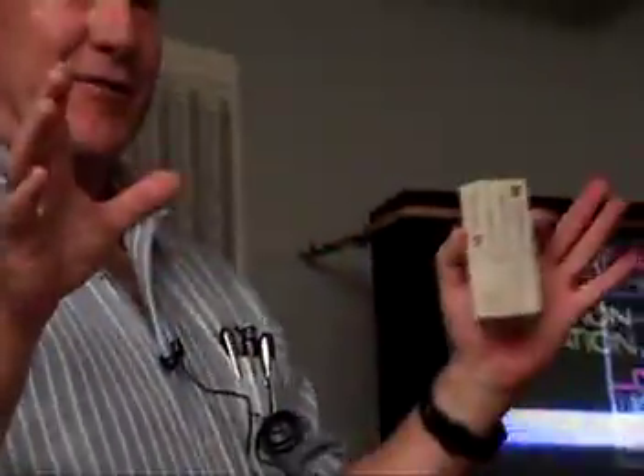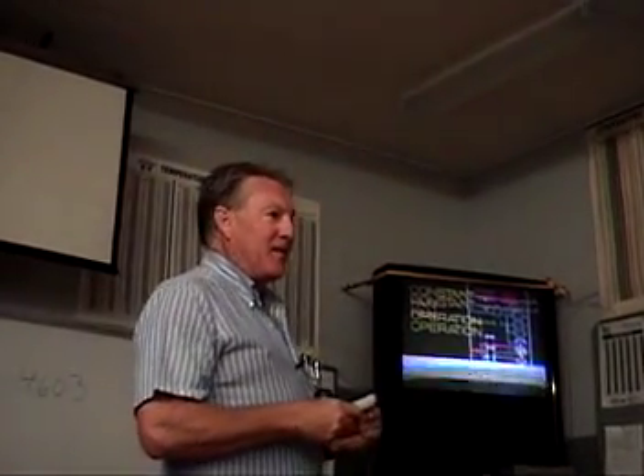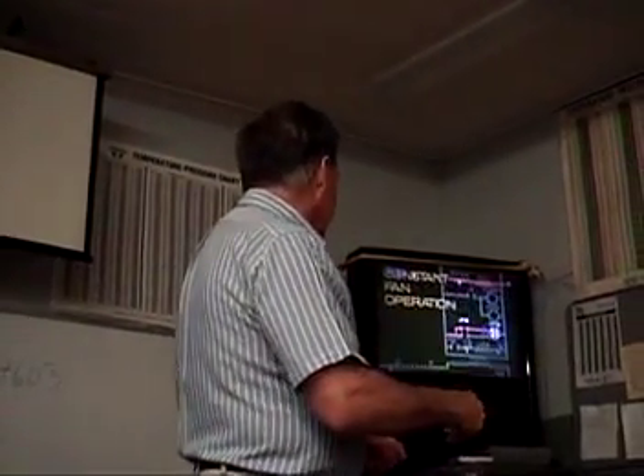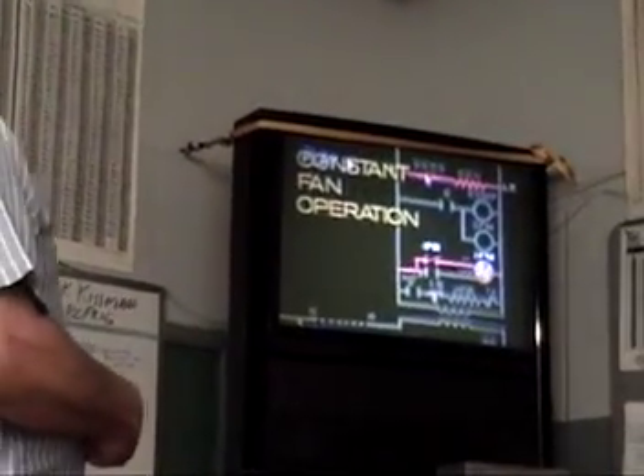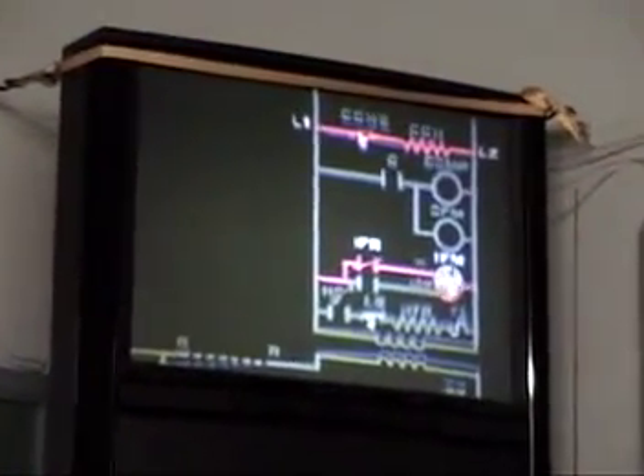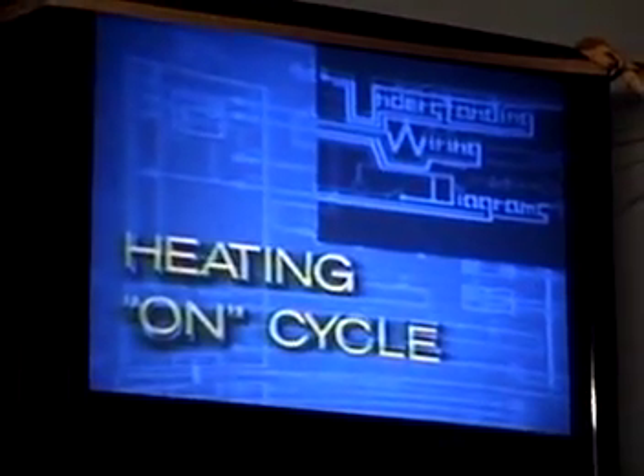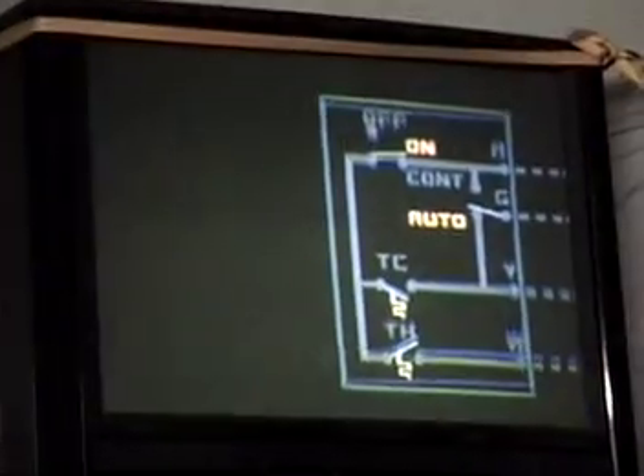Okay, now when I check you off on your competency for wiring up your fan, a couple of you guys, you had it on fan continuous, not auto, and the fan was running like it was supposed to, but it wasn't wired correctly. I switched it to auto, everything went off. It's supposed to be on. Little problem, but you guys are all working it out really good. If the outdoor air temperature stays below 65 degrees, the crankcase heater will stay energized. When heating is required, the thermostat is set to the desired temperature.